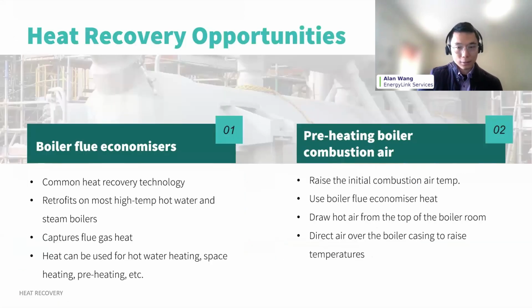which, if you look at the next slide, is the boiler flue gas economizers. So in a natural gas fired boiler, if the flue gases exit around, say, 180 degrees Celsius to 200, by installing an economizer, you can recover a portion of this waste heat to preheat the boiler feed water, raise the boiler feed water temperature. Depending on the application, this can then reduce fuel consumption by 5 or sometimes even 15% in some extreme cases. And in larger systems, that could mean several hundreds of gigajoules saved per year per megawatt of boiler capacity.